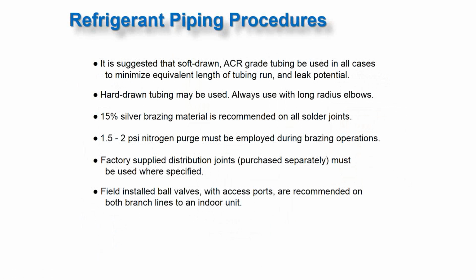A lot of times it's 1/2 inch insulation, but in New York City now, I think there are some areas where they're asking for 1 inch thick insulation on your line sets. You can use hard ACR copper, but you have to use long radius elbows when you're using hard pipe. When you're brazing, especially hard pipe, you want to use 15% silver solder, and you want to use a nitrogen purge. You can use a 1.5 to 2 psi purge through your pipe when you're brazing.